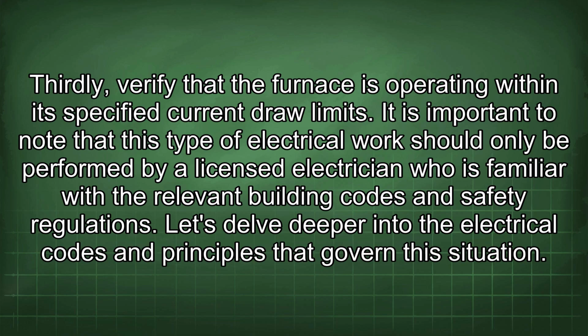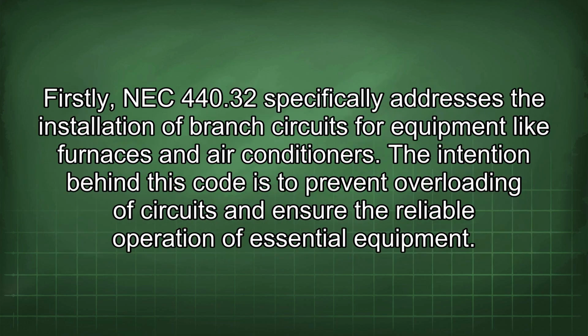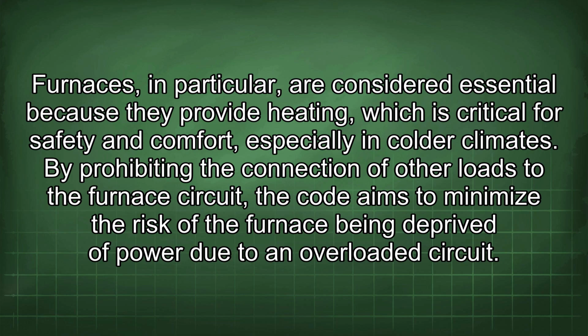Let's delve deeper into the electrical codes and principles that govern this situation. Firstly, NEC 440.32 specifically addresses the installation of branch circuits for equipment like furnaces and air conditioners. The intention behind this code is to prevent overloading of circuits and ensure the reliable operation of essential equipment. Furnaces, in particular, are considered essential because they provide heating, which is critical for safety and comfort, especially in colder climates. By prohibiting the connection of other loads to the furnace circuit, the code aims to minimize the risk of the furnace being deprived of power due to an overloaded circuit.